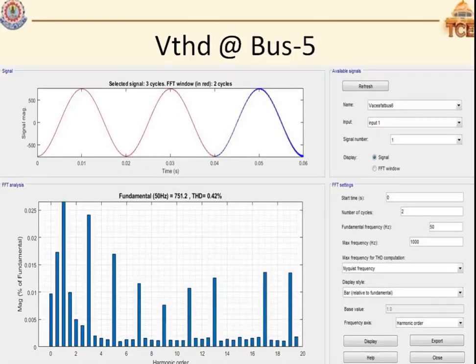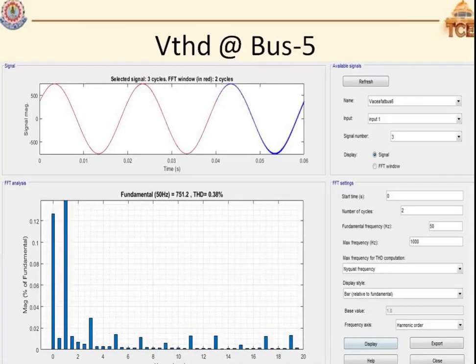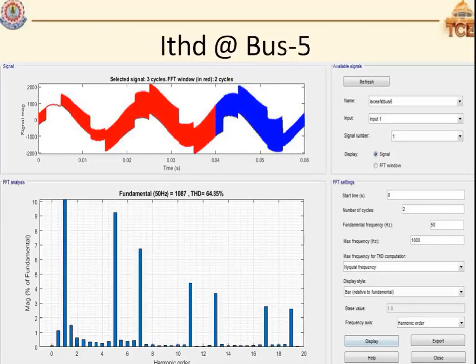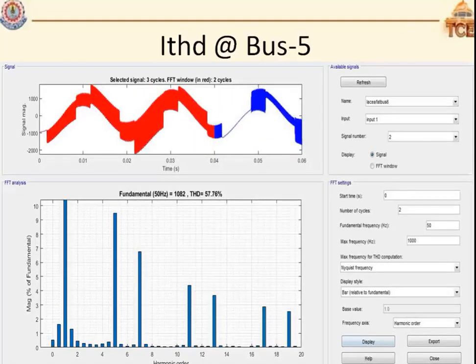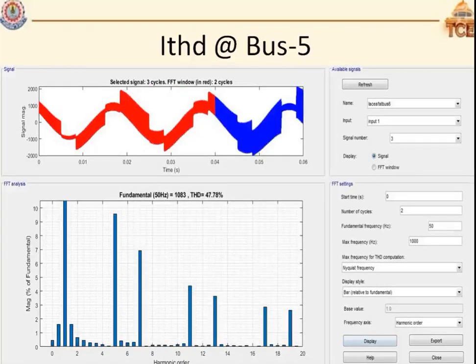This is the voltage THD. Here we see that several order harmonics were present, but in little amount. The voltage THD is about 0.42% at phase A. This is about phase B, about phase C, and this is the current THD, which is more than 64.85%, a very high percentage according to the TNEB standards. The current THD should be limited to only about 8%, but it is about 64.85%. Is this for phase B? This is for phase C.